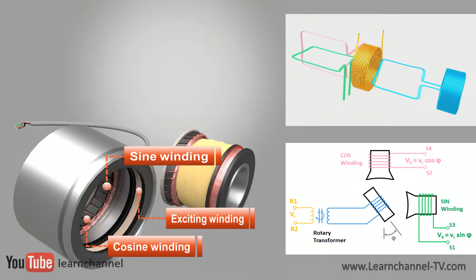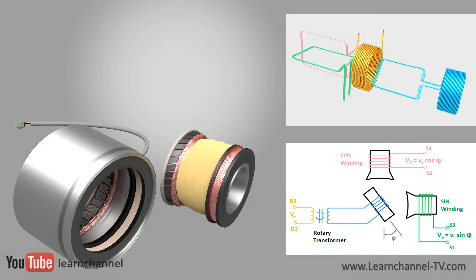Furthermore, we can name the rotor winding also as reference winding. The relative magnitudes of the sine and cosine voltage are measured to determine the angle of the rotor relative to the stator.